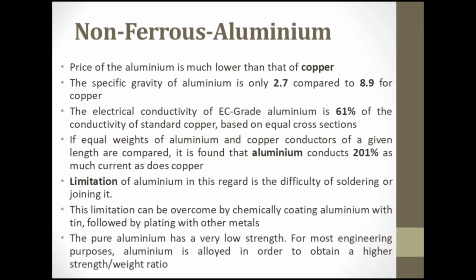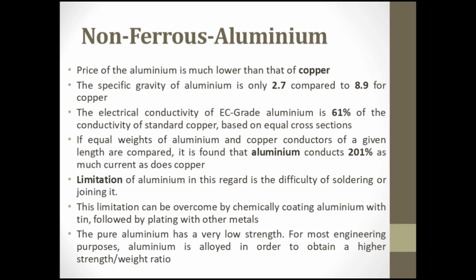Non-ferrous aluminium. The price of aluminium is much lower than that of copper. The specific gravity of aluminium is only 2.7 compared to 8.9 for copper. The electrical conductivity of EC grade aluminium is 61% of the conductivity of standard copper based on equal cross sections. If equal weights of aluminium and copper conductors of a given length are compared, it is found that aluminium conducts 201% as much current as does copper.